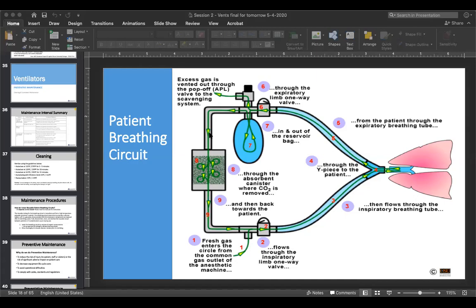So as long as you have 2 HME filters in the circuit at the spots where we talked about earlier, one by the ETT, or the endotracheal tube, the other one right before the APL valve, the machine should be safe for reuse. Again, after each patient, we recommend discarding the filters and disinfecting the machine, as well as sterilizing the reusable circuit.